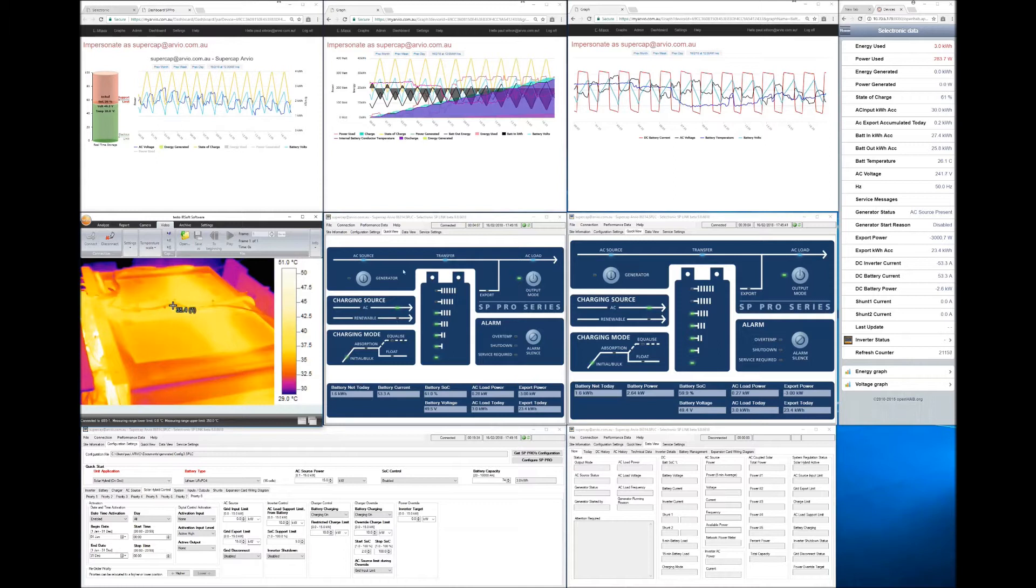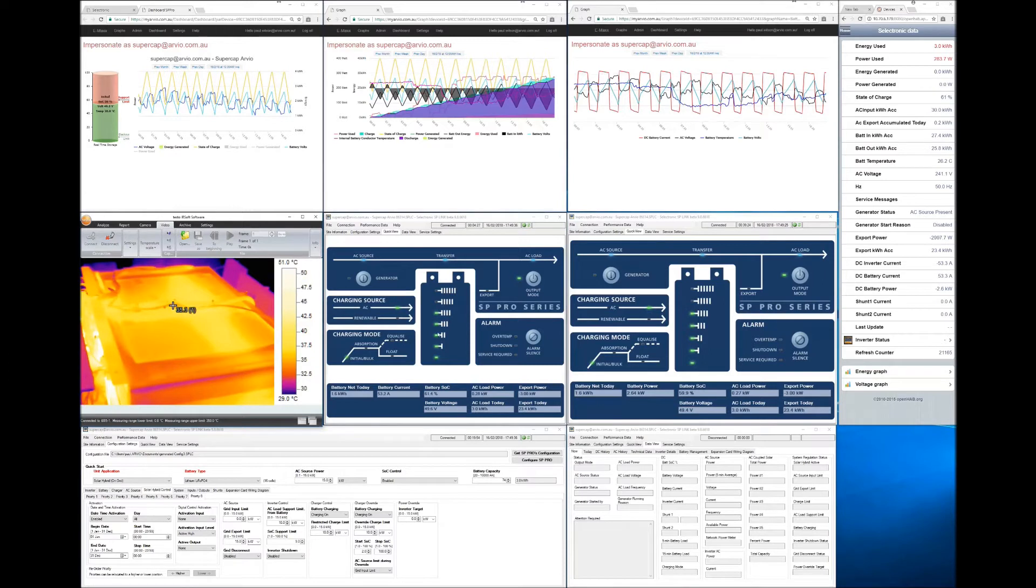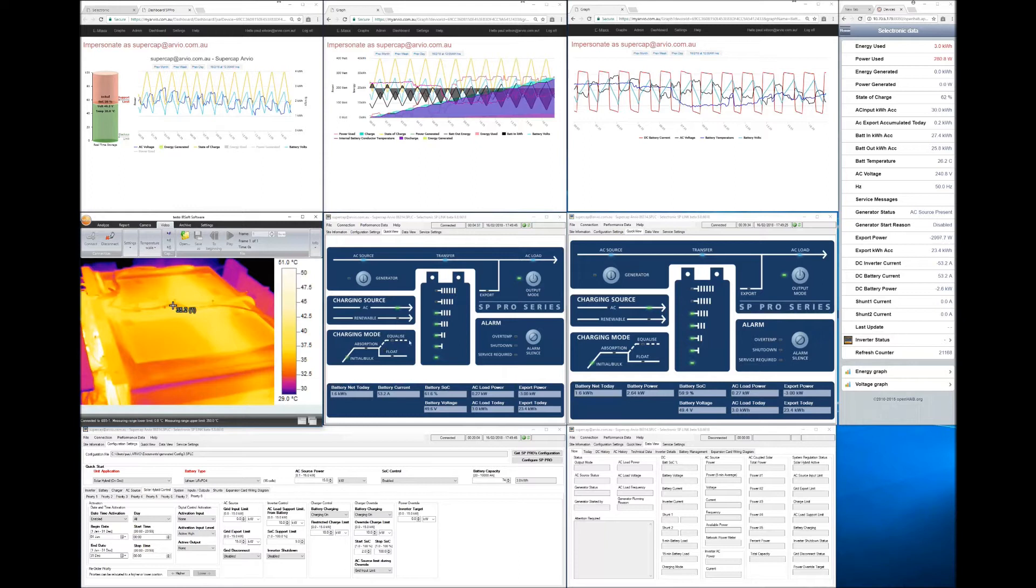So over here we've got a log into the inverter which is showing at the moment we've got an AC source which is the grid. In Australia that is around 240 to 250 volts AC. And we are taking that energy and we are transferring it to an AC load. And at the moment we are charging with this AC source into the supercapacitor. And that's happening as what we call an initial or bulk charge. So normally a chemical battery goes through an initial bulk charge, absorption charge, an equalization charge or float charge.